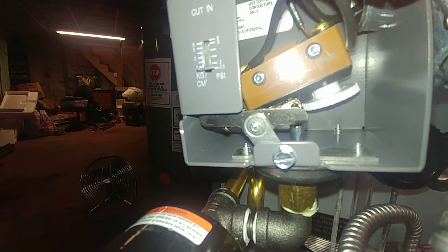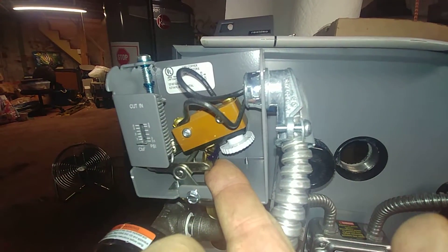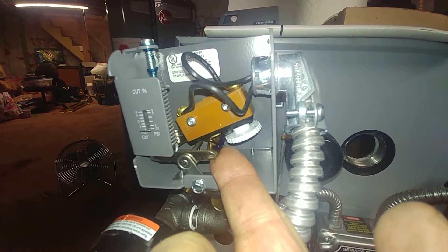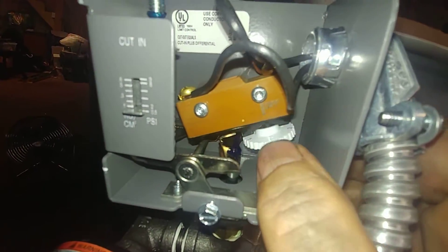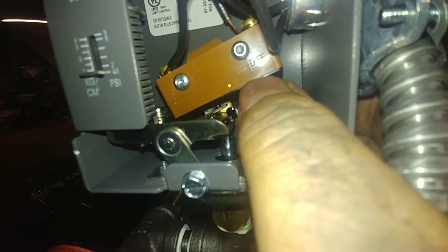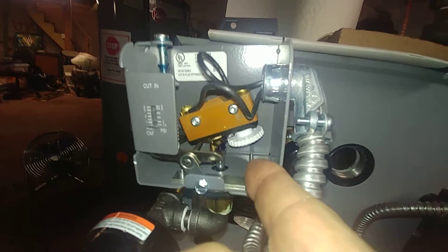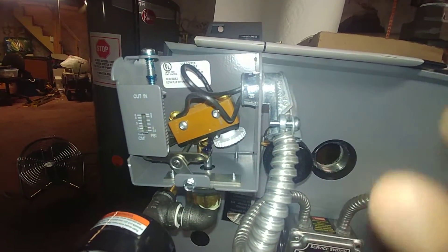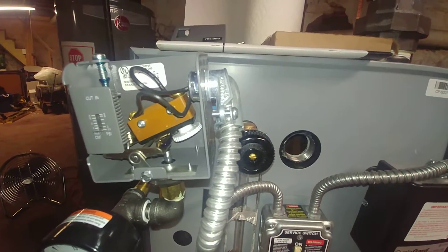I think you can see that 0.5, below the two. Let's do the finger test here — there we are, that's not bad. We want to set the differential — DIFF right there — to one, and we want the main setting bottomed out. That should be about a pound and a half, but it's probably more or less.